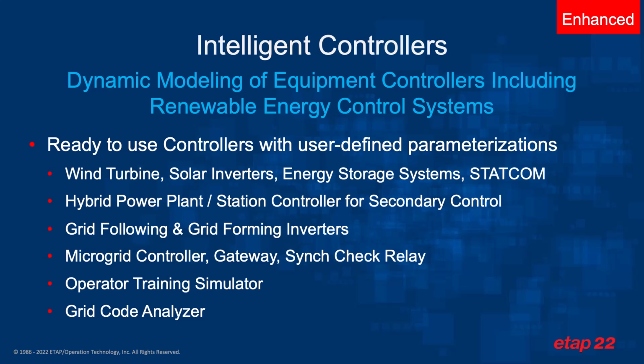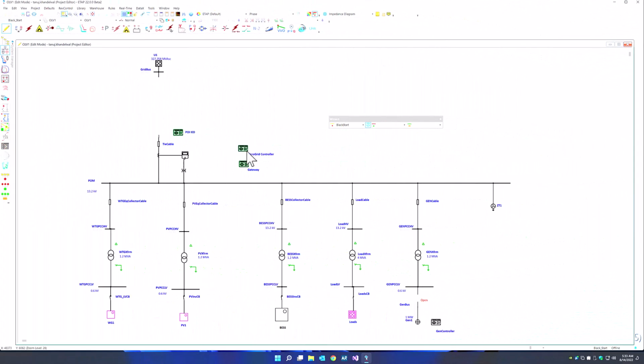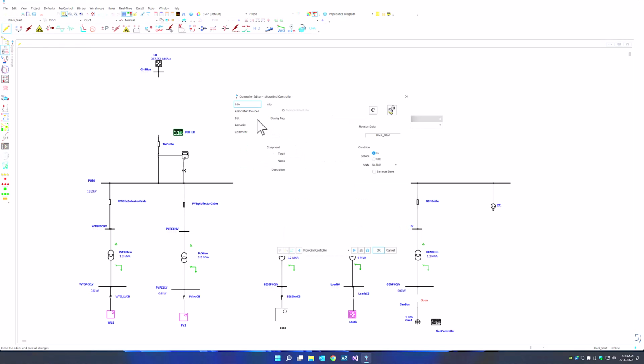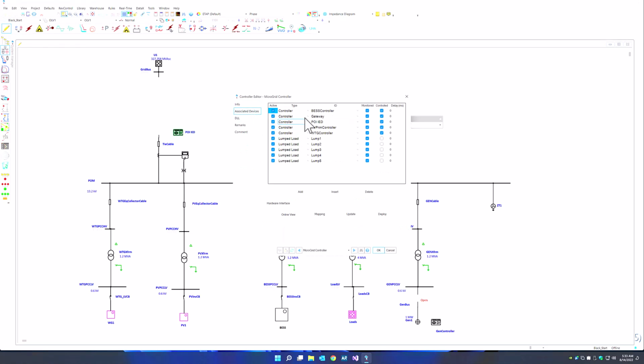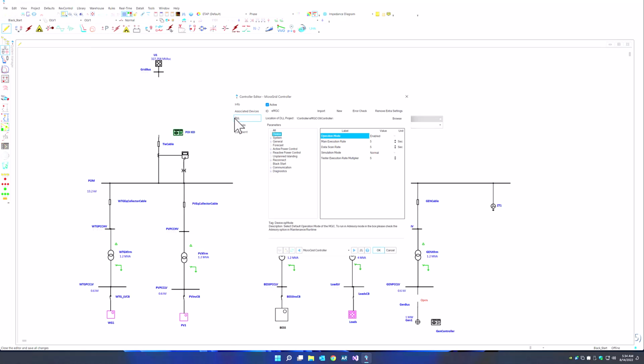So let's take a look at some of these controllers in action. The controllers can be dragged and dropped from the system toolbox. You can double click and open the controller to see which devices you are monitoring or controlling and adjust them. You can also pick what DLL is being used for this particular controller. A DLL stands for Dynamic Link Library, and it's essentially the black box implementation of the control system.